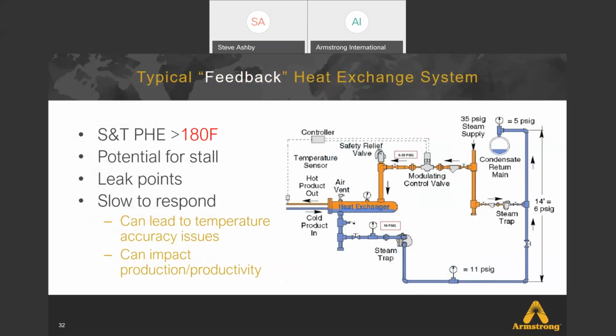Okay, so here again is our typical feedback heat exchanger. Got a lot of parts and pieces going on here. Steam control valve on the inlet side of the heat exchanger, a controller and a temperature sensor. Then your heat exchanger, your traps, a lot of times pumps. But what is surprising is a lot of times in this setup, there are no pumps.